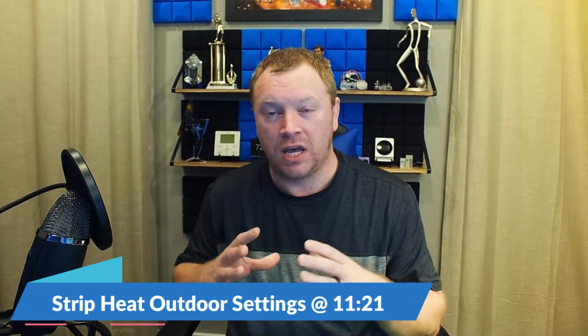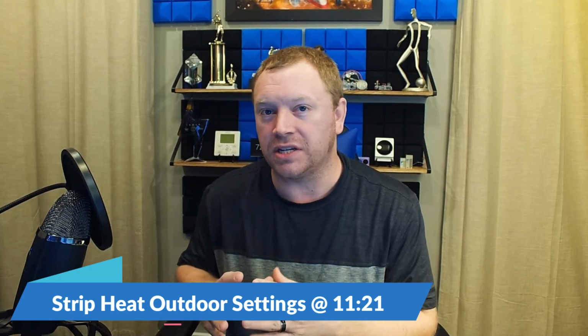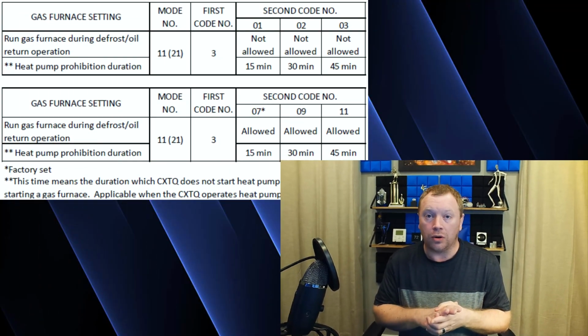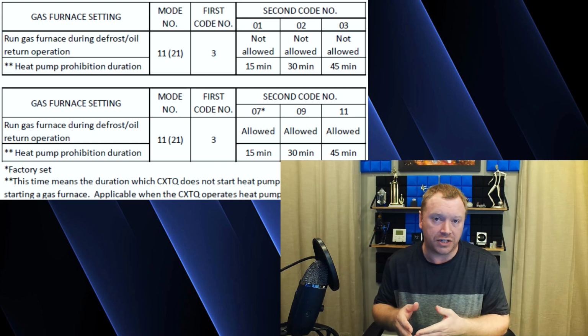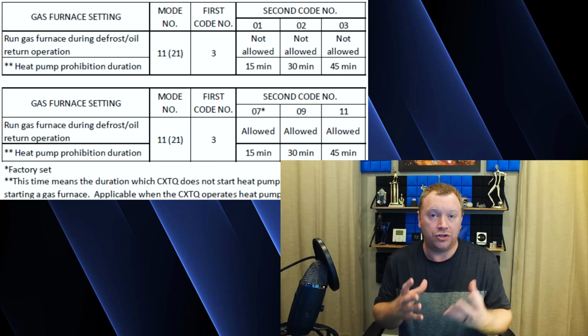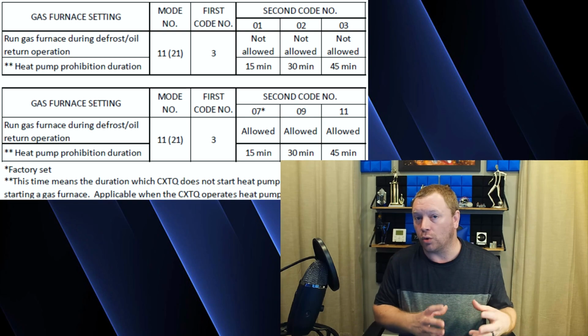When you're ready to program the gas furnace field settings, there's actually fewer settings that you need to program here, because you're not going to tell it what size your gas heat is. You don't need to do that. And you also don't need to tell it whether or not you want to run the gas furnace with the heat pump, because you can't run the gas furnace and the heat pump at the same time on that CXTQ 8-coil zone. On that unit, it's one or the other. So your first setting that you're actually going to need to set is just, do you want to run the gas furnace during defrost or not?